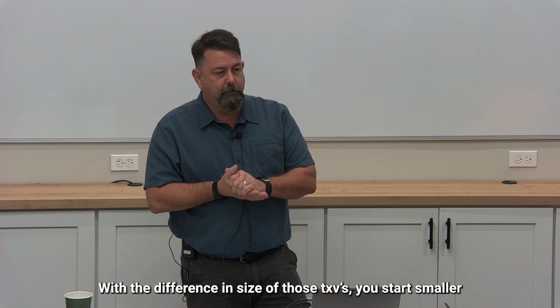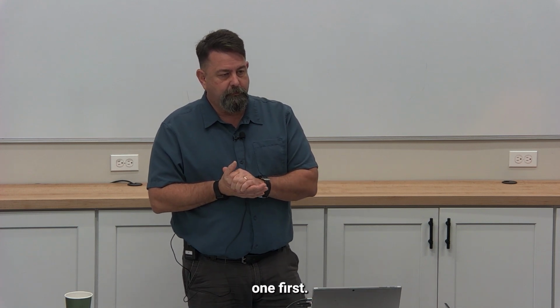With the difference in sizes of those TXVs, you start with the smaller one first. Sure, yeah, best practice. Now, just remember that, anytime I'm checking superheat, I can do that too, right? If I'm not sure, we're going to go farther down and take a reading. That may not be practical, depending on how the piping runs. It might pump out of the rack house right there and disappear, whatever. I can always just turn them off. I can always shut them both off, as long as I've got some heat on that drop leg, then turn one on and check that superheat and watch it fall, right? That's the other way to check it. Either method will show me a flood.